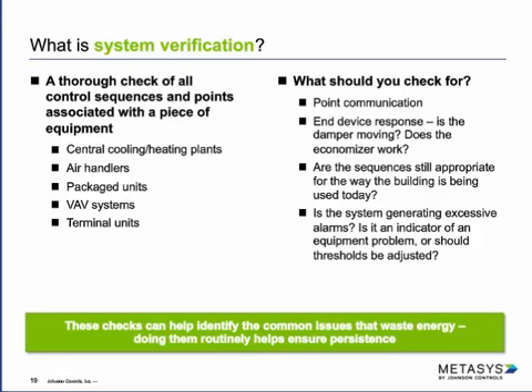These checks really need to be done on a routine basis, because unlike an equipment retrofit, once you replace equipment, it stays replaced. If you change or enhance a control sequence, there's always an opportunity for somebody to undo it. So it makes sense to routinely go through these systems. Also, your building changes, the way you use it changes, the spaces may be different, the hours of operation may be different. That's another reason it's important to put these reviews on a regular schedule. We've seen that quite a bit, as tenants change through a building floor to floor, or site to site, or occupancy to occupancy.